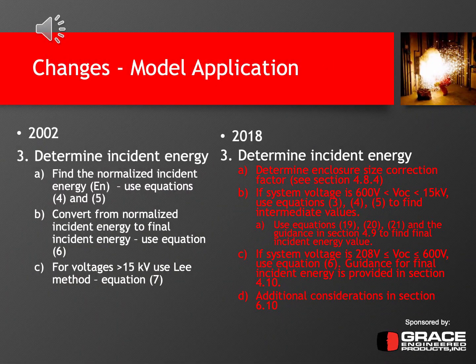So once the arcing current and arc duration or fault clearing time are known, you then need to determine and calculate the incident energy. In 2002, basically there were these 3 steps listed here. Step A was to find the normalized incident energy using equations 4 and 5, and then step B was to take that normalized energy and convert it to a final incident energy by using equation 6. And for voltages that are greater than 15 kV, the 1584 2002 edition recommended using the Lee method, which was equation 7. I won't go into details on the Lee method, but that was kind of how it was done in 2002.